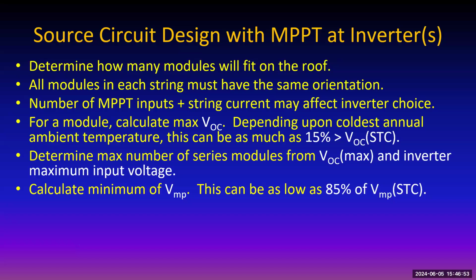And if you do maximum power point tracking at the string level, that means the strings are connected in DC in series, as we discussed earlier. If one module is shaded, it's going to change the power output. With straight inverter-level design, with the maximum power point tracking at the inverter, you can't do what you can do with optimizers and microinverters. You can't put modules facing in different directions and have them in the same string. You can do that with microinverters and with optimizers. They optimize their output individually, and they don't affect each other. But modules do affect each other if you don't have these cute little boxes in between.